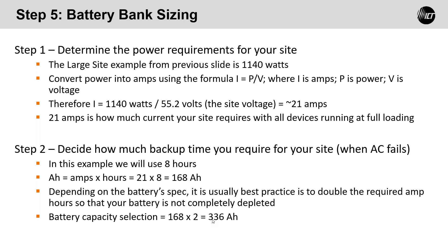Now we want to determine how long it's going to take to recharge that battery based on the power supply. So if we assume we have 3 700-watt power modules, 3 times 700 is 2100 watts. That's how much the rectifier is going to give you. And if we divide that by 55.2, we end up with 38 amps. And now if we take the load, the 1140 divided by, as we did earlier, 55.2, we get 21 amps. And now, if we take 1/2 of the battery amp hour rating, 168 amp hours, in order to determine how long it's going to take, the load is 21 amps.